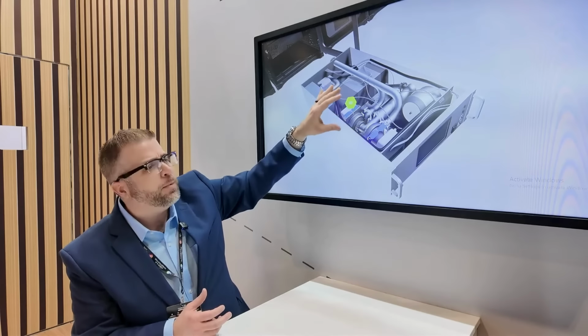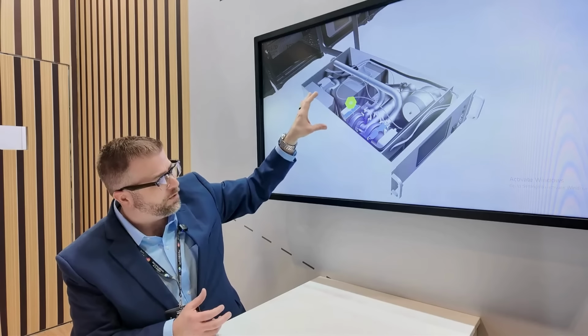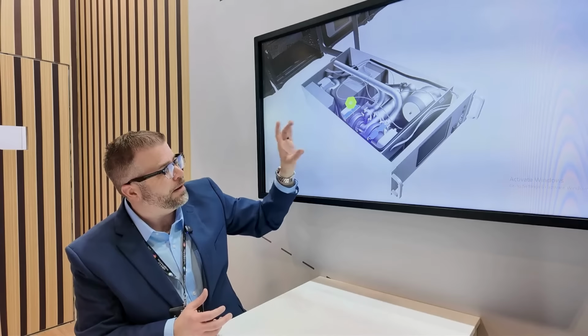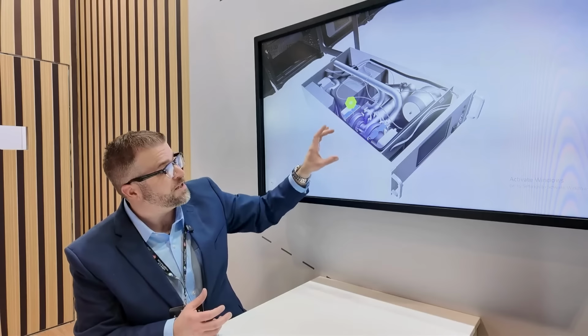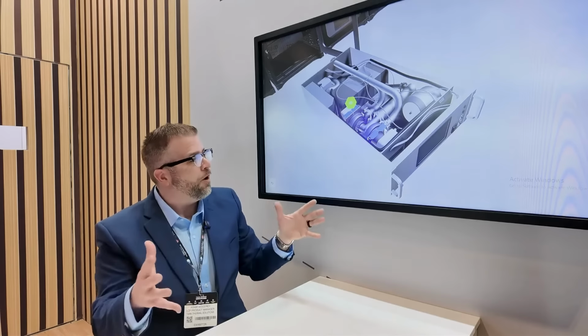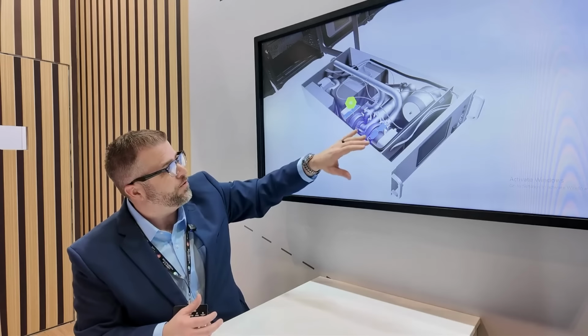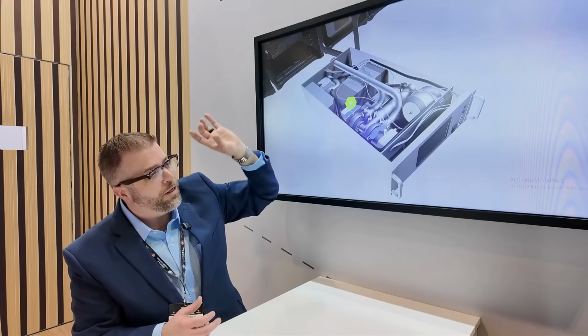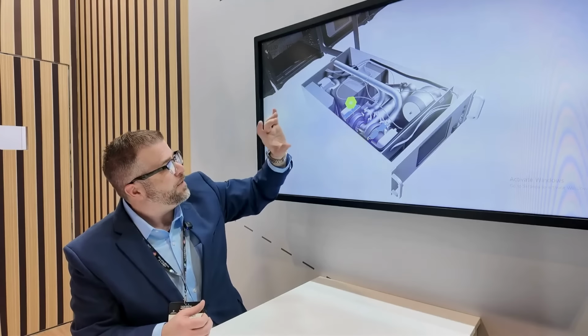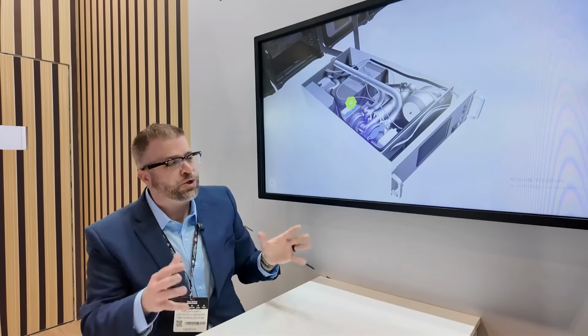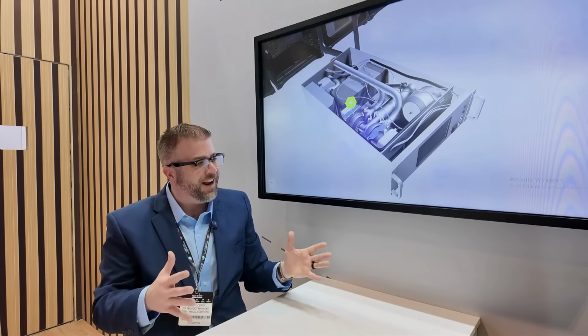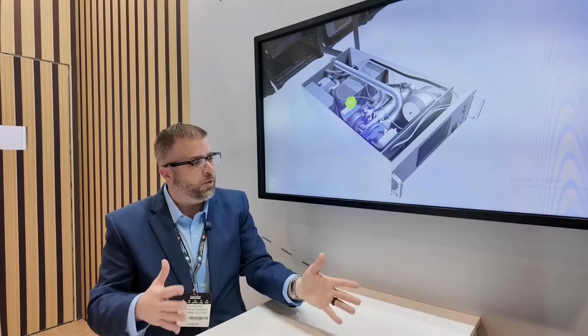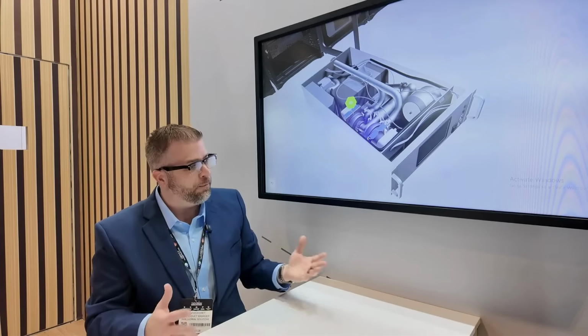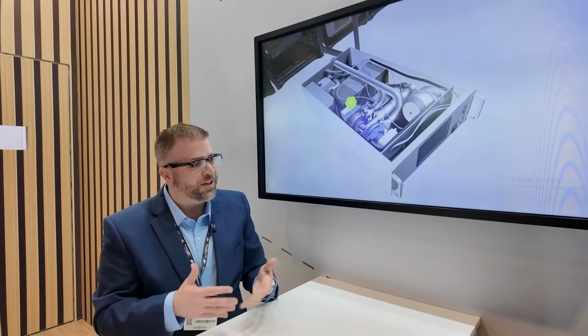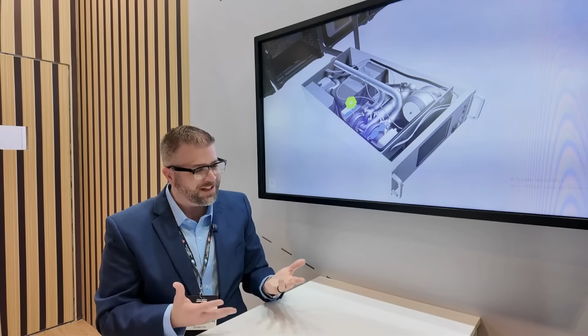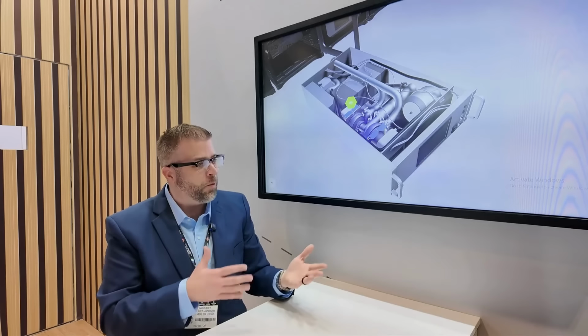Now, the fans may still be required throughout the CDU itself, but not needing those fans to be dedicated to the pumps allows more operating area for the fluid delivery network, the piping schematic, whether it is the heat exchanger, filters, accumulators. You now have more real estate to dedicate towards what is important to the CDU itself, not simply focusing on the pumps. And that combination is what we are excited to bring to the market with the TCDU series, and looking forward to where we go next.